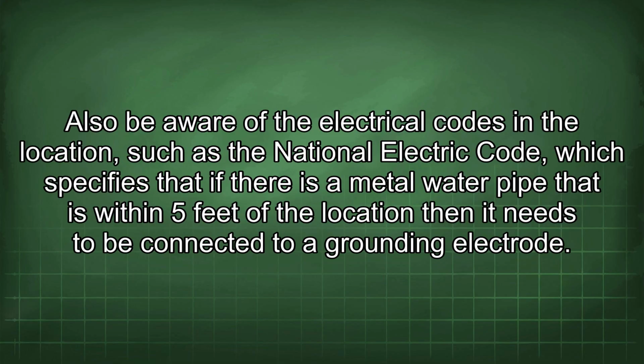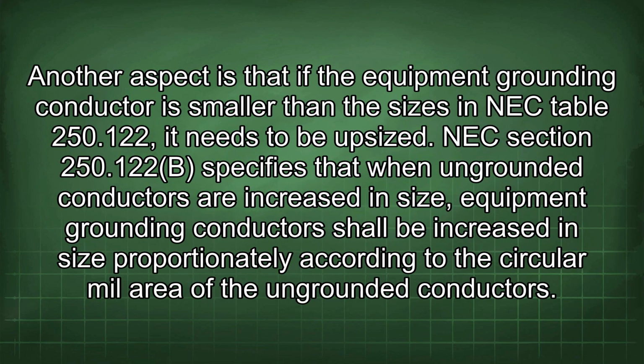Also be aware of the electrical codes in the location, such as the National Electric Code, which specifies that if there is a metal water pipe that is within 5 feet of the location, then it needs to be connected to a grounding electrode. Another aspect is that if the equipment grounding conductor is smaller than the sizes in NEC Table 250.122, it needs to be upsized.